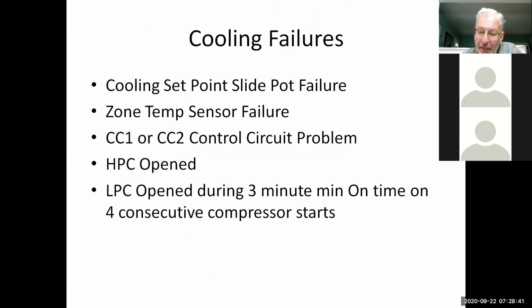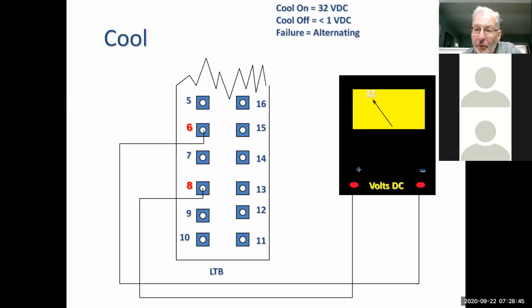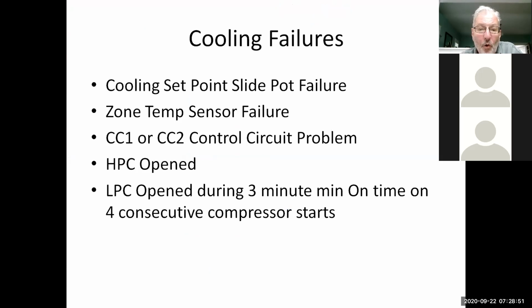If it's alternating between 0 and 32, that means you're in a cool fail, okay? When you're in a cool fail, it could be a slide pot failure on the thermostat. It could be a zone sensor failure. But typically, it's contactor 1 or contactor 2, or the high pressure or low pressure switch is open.